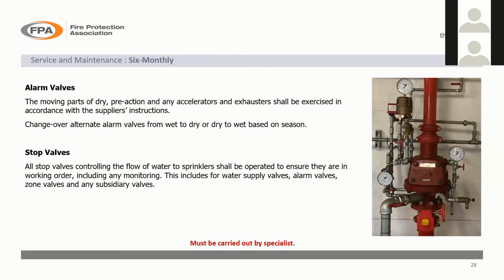And that, on a quarterly basis, can only be carried out by a specialist. So six monthly, obviously, your alarm valves and your stop valves need to be operated and checked, and any changeover from alternate systems, when you change from a wet system during the summer to a dry system during the winter, would be done on a cyclic monthly basis. And all your stop valves controlling the flow of water to the sprinklers should be operated to ensure they're in working order. This includes any subsidiary zone valves.